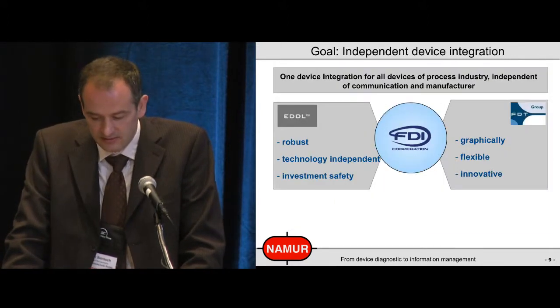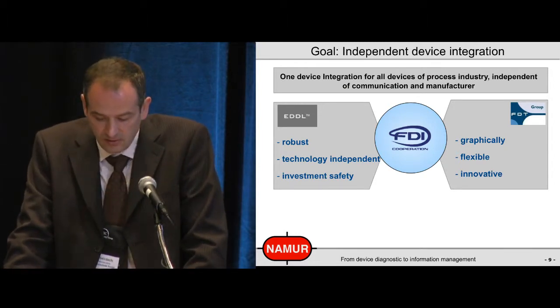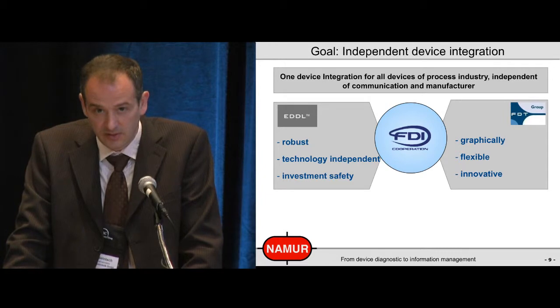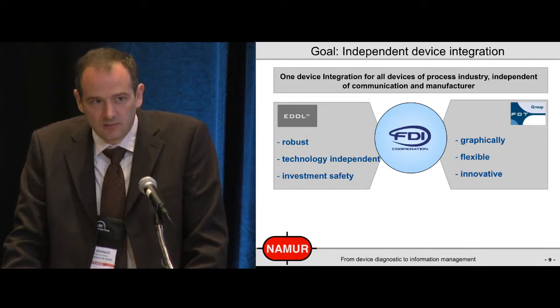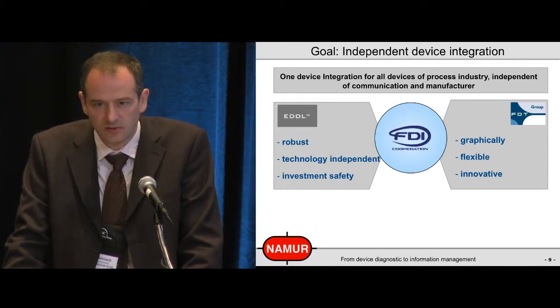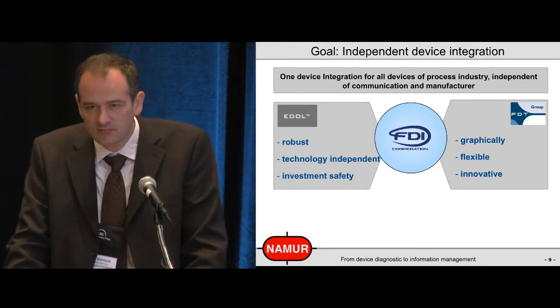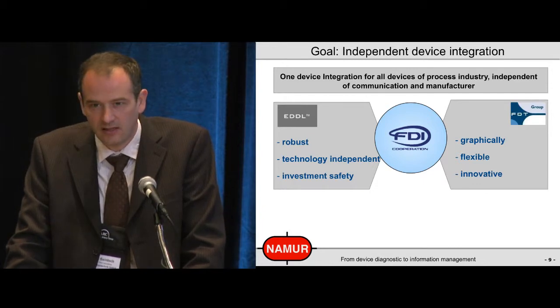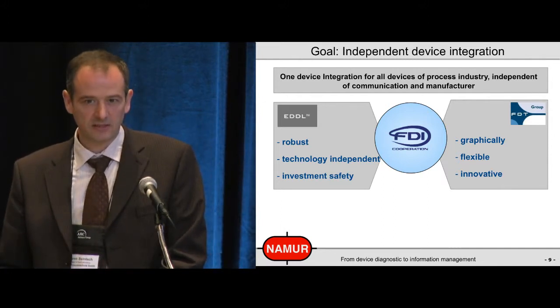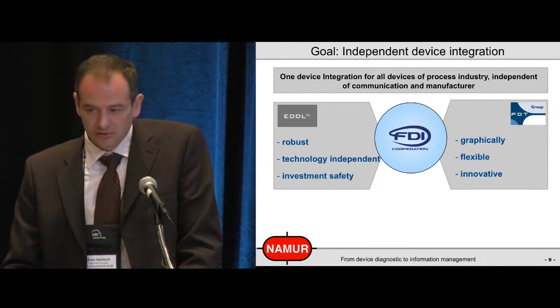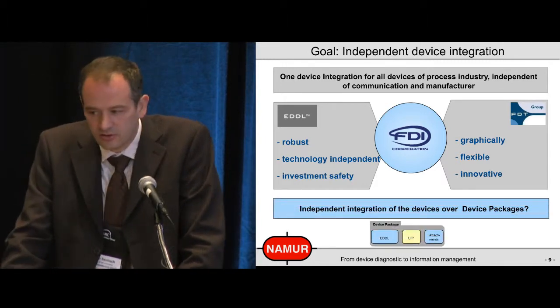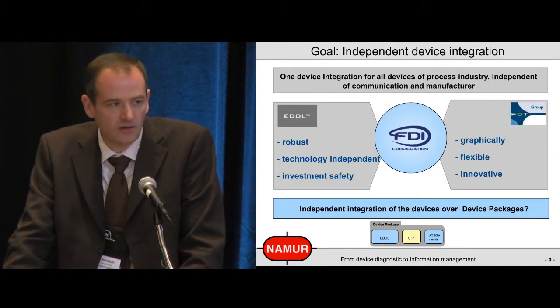The goal must be an independent device integration so that you have just one device integration for all devices used in the process industry, independent from the communication and the manufacturer. And that's the point where FDI — field device integration — comes up. On one hand you have the EDDL side, which is very robust, independent from operating systems and therefore investment safe. And on the other hand you have the FDT side, which is graphical, very flexible and innovative. So we should combine these good points of both technologies and reach an independent integration of devices over device packages.